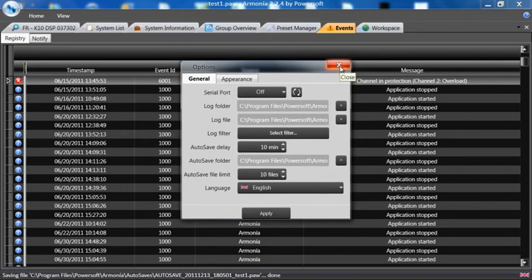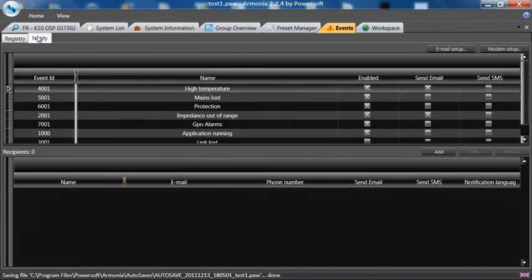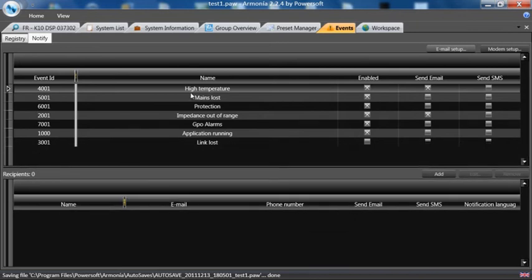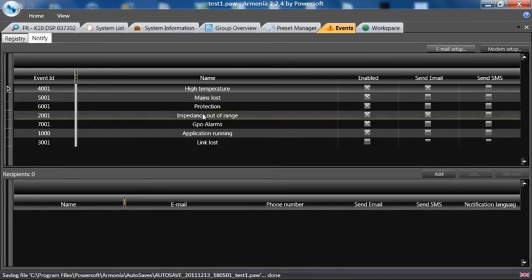If we go to the Notify tab at the top, this shows the error codes that might occur: high temperature, mains lost, protection, impedance out of range. That is a difference of 25% of the reference impedance.